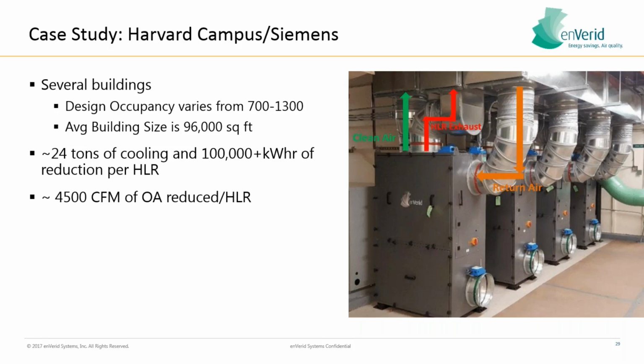So massive energy savings, massive utility rebates here, and phenomenal air quality as well for the 700 to 1,000 occupants within this space. Okay. You can see unducted down here. We have this damper as well. We're actually able to use mechanical room air for that purge cycle when we're exhausting out that HLR exhaust. We're scrubbing at any given time about 700 to 1,000 CFM through each unit, okay? So these are 700 to 1,000 CFM units. They can treat 20,000, 25,000 CFM air handlers because we're a side stream application. We're not scrubbing 100% of the return. And when we purge these units to keep the building from going negative, we just exhaust that air at about 250 CFM, okay? So it's a slow bleed purge when we're going through regeneration.